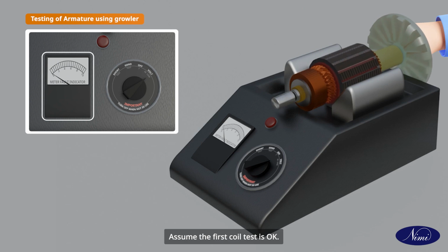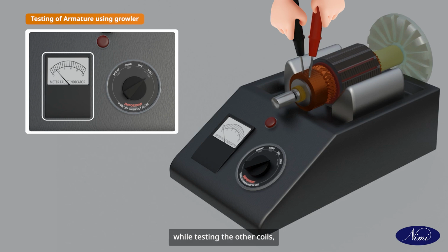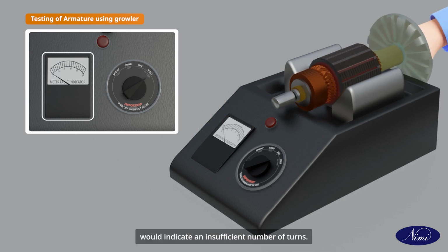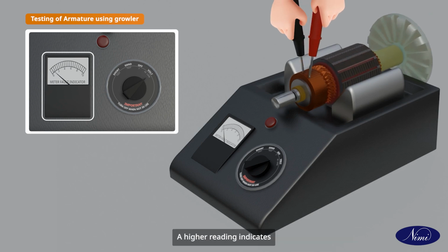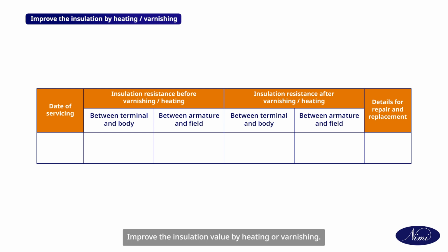Assume the first coil test is okay. A lower meter reading while testing the other coils would indicate an insufficient number of turns. A higher reading indicates there are too many turns in the coil. Improve the insulation value by heating or varnishing. If the insulation value is less than 1 megaohm, then enter the test results in the maintenance card.